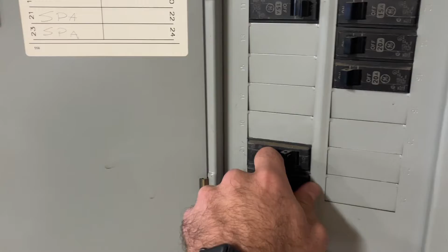So I'm going to turn it off for a full 15 minutes to make sure everything fully drains of power and resets, then come back and check. Turning off, I'll be back in 15 minutes. Now turning it back on, let's go check and see if that helped. There's been no change after the power being off for 15 minutes.